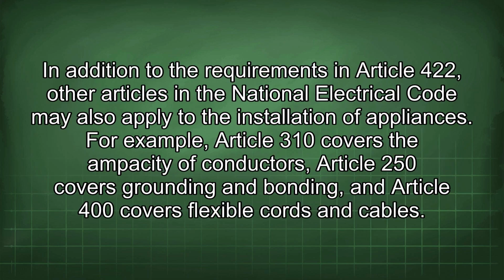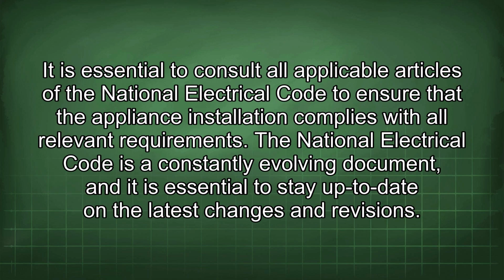In addition to the requirements in Article 422, other articles in the National Electrical Code may also apply to the installation of appliances. For example, Article 310 covers the ampacity of conductors, Article 250 covers grounding and bonding, and Article 400 covers flexible cords and cables. It is essential to consult all applicable articles of the National Electrical Code to ensure that the appliance installation complies with all relevant requirements.